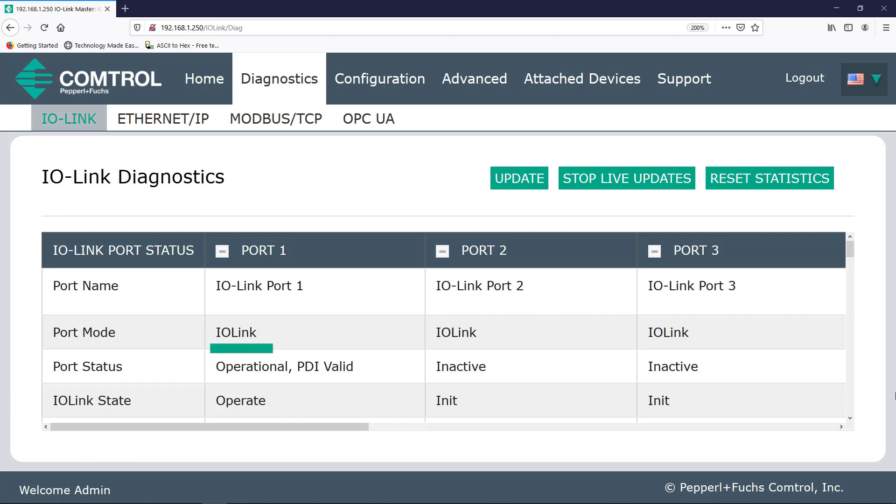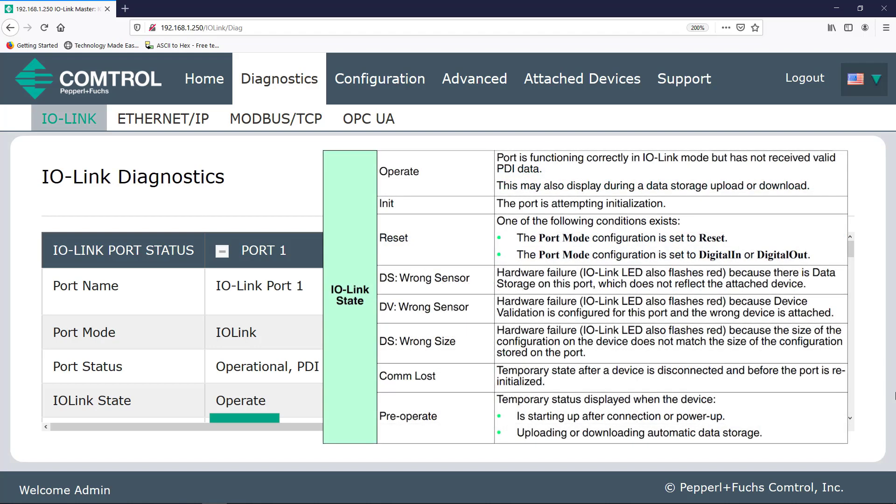You can change this on the Configuration tab. And if this were to say reset, it means you've probably disabled this port. Next, we see that the port is operational and the process data input is valid, even though we haven't read a tag yet. IO-Link state is listed as operate, which means that the port is functioning correctly in IO-Link mode.